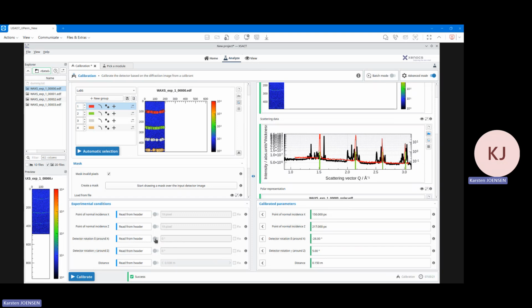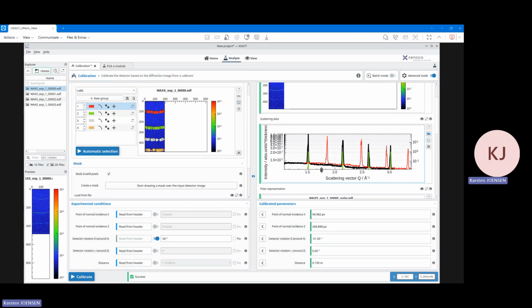So to fix that and to actually make it effective, we're going to go into what the nominal was here, which is actually 5 above this value here, minus 31, 32. And I'll just show you that here, in this case it arrives at basically the same. Now what I want to do for the workaround is to go up to a number that is higher than 5 times what I suspect the value would be, and then actually try to run that. Now, what that does is the red you can see does not match the calibration lines because it's clearly not 36. But the value that's found is 31 and actually does begin to look nicer.